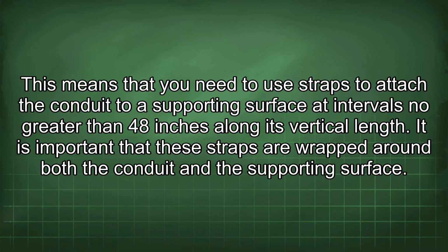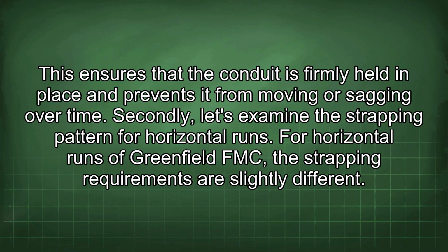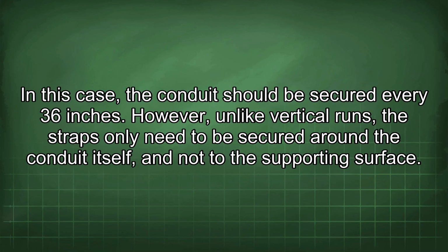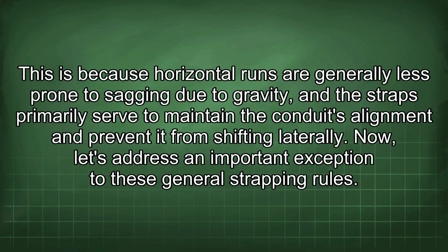It is important that these straps are wrapped around both the conduit and the supporting surface. This ensures that the conduit is firmly held in place and prevents it from moving or sagging over time. Secondly, let's examine the strapping pattern for horizontal runs. For horizontal runs of Greenfield FMC, the strapping requirements are slightly different. In this case, the conduit should be secured every 36 inches. However, unlike vertical runs, the straps only need to be secured around the conduit itself and not to the supporting surface. This is because horizontal runs are generally less prone to sagging due to gravity, and the straps primarily serve to maintain the conduit's alignment and prevent it from shifting laterally.